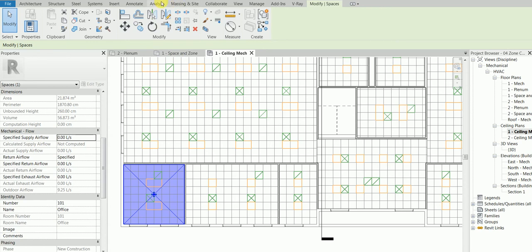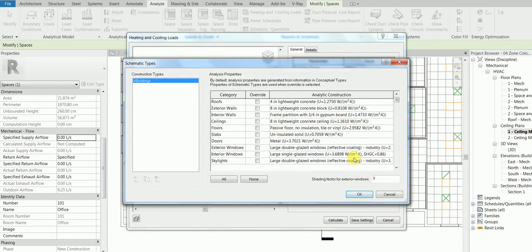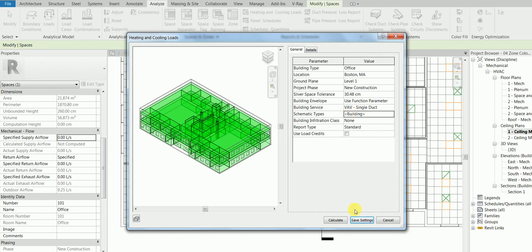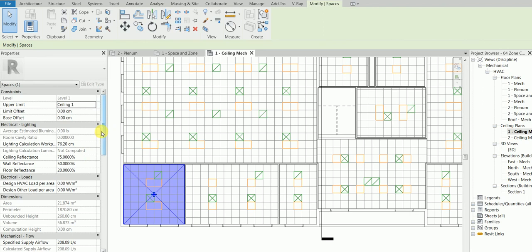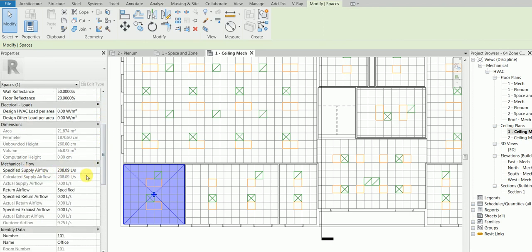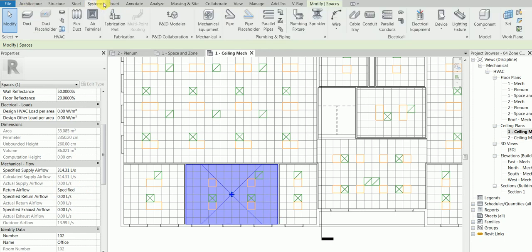Go to the Analyze tab, Heating and Cooling Loads, change the settings — the building type, override whatever you need — and then click Calculate. After Revit finishes the calculation, the space properties that previously showed 'Not Computed' will now be filled in with calculated values. Once you click the same space again, you'll see the specified airflow — for example, 208 liters per second — while the actual airflow shows zero because no air terminal has been placed yet.